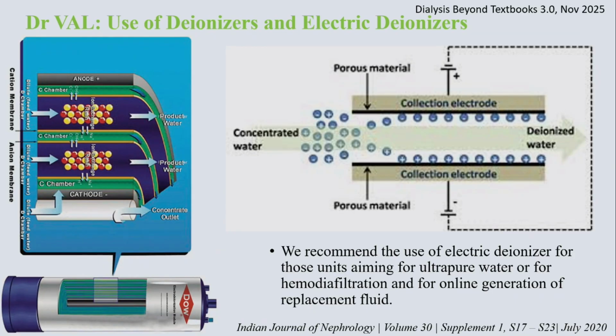A word about UV you want to say? Like what wavelength should we use for what purpose? It's not only the wavelength. We put this in the ISN guideline on water treatment, that one is the wavelength is different. The second is that chloramines require an energy input in terms of joules per mole, which is about 30 times that for chlorine. So you may not be able to depend only on UV unless you can size your UV to deliver about, I think, 600 millijoules per second of radiant energy is the rating recommended. I can't remember it offhand. It's there in the guideline. And that is what is required for chloramines. It then also takes care of your organochlorine pesticides, fertilizers, and so on in such a situation.